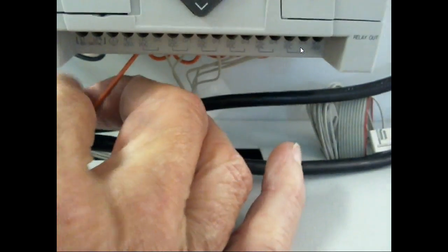Y'all understand that? So what you would do is bring your neutral and jump it down through all these commons. Y'all might not can see this, but here's all my little jumps right here. Can y'all see it? So here comes my power supply. This is my plus, so I have it hooked up for sourcing, and then I have it hooked up to the common of all those outputs. So on mine, I have the outputs hooked up for sourcing, and I have my inputs hooked up for sinking.